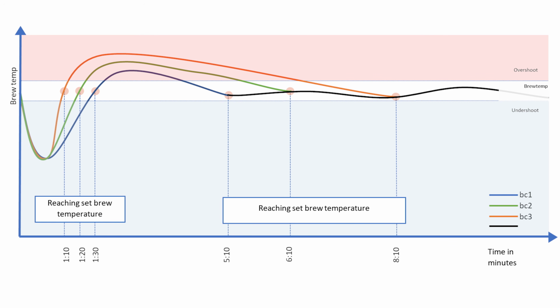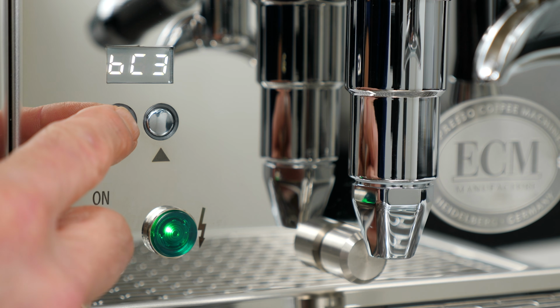In this ECM test result graph, you can see the effect of the different brew control modes following an extraction. Notice BC3 recovers to set temp and is ready to go after 1 minute 10 seconds. But if you don't pull a shot, heating overshoots and it's a little over 8 minutes until temps are stable again. At the other end, set to BC1, initial recovery takes 1:30. But let it go and overshoot is less at just a little over 5 minutes until temps are fully stable again.